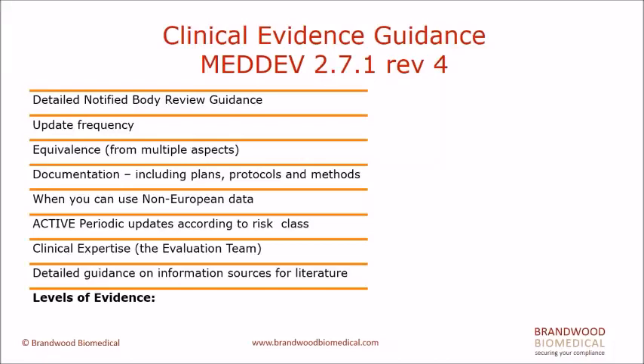So here we have a merger, a coming together of the European regulations and the US regulations. The 510K process in the United States has been built on the concept of substantial equivalence for a very long time now, back since 1976, and here it is written into the European regulations. We now have a guidance here that says you can do clinical evaluation of a medical device, but you have to compare equivalence not just on the clinical performance, but you have to show that you're equivalent to the predicate device in terms of the technology, the physical performance and characteristics, and the biological safety, the biocompatibility. All of that has to be done, and it's in the guidance in detail. There's detailed guidance on how to document all of this, the need for plans, protocols, methods.